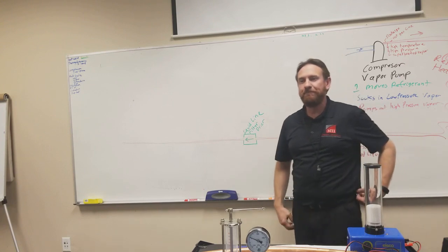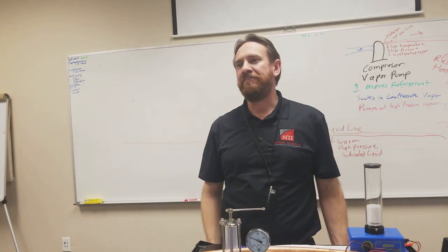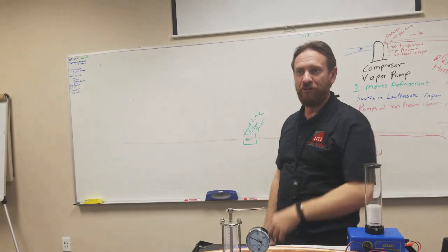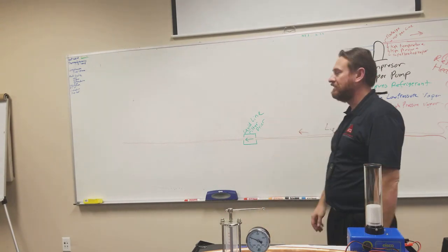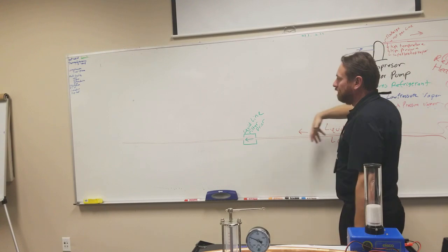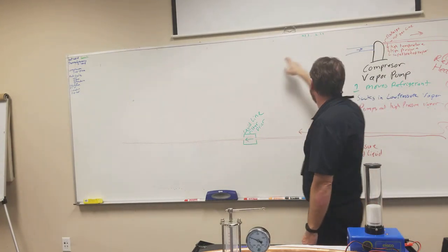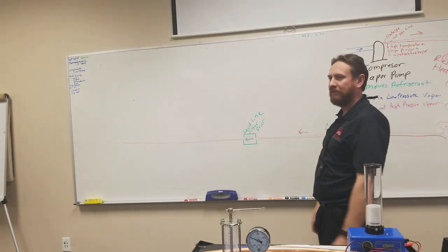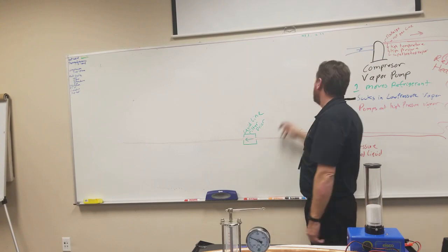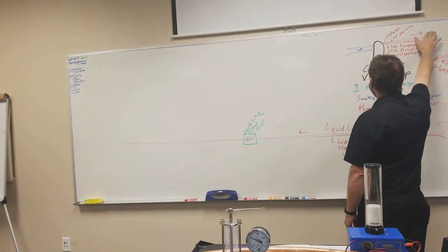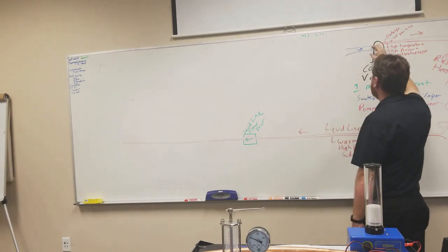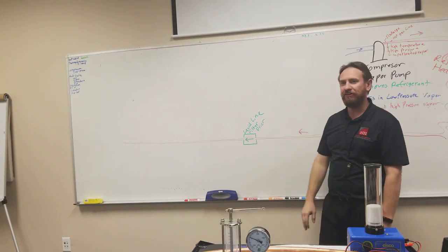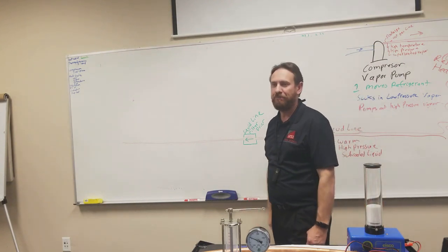Is that the only thing that can make it go bad? No, there's many other things that can make it go bad. There's people that put their gauges on, had contaminants in their hoses, they put them on this unit, now there's contaminants in here. Also, people that didn't pull a good vacuum, it caught all the moisture it can, but now the moisture that's in there turns to acid. The acid starts eating away the compressor and the copper pieces, and those will start building up and clog it up. Compressor failures, running the unit without the fan motor causes high pressures. This will break down. All those contaminants can clog up in here. And we'll talk about how to check this later on, but there's several things that can cause it to go bad.